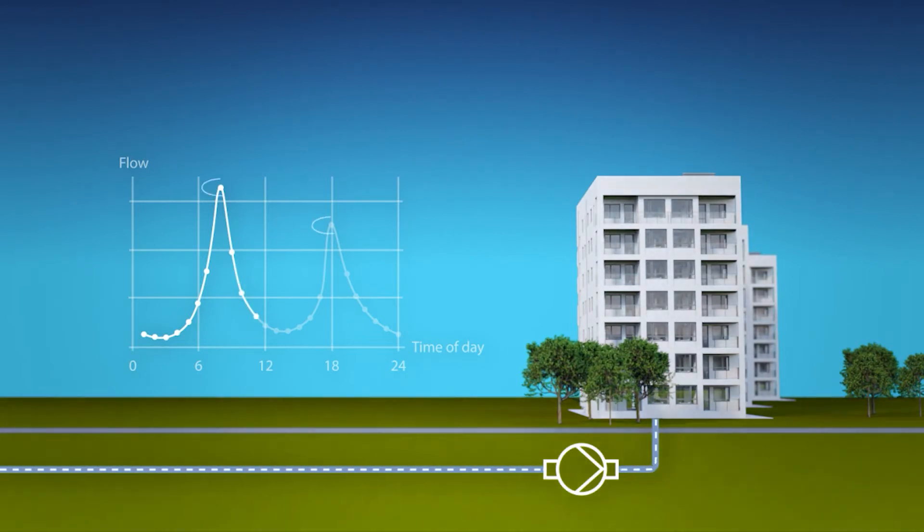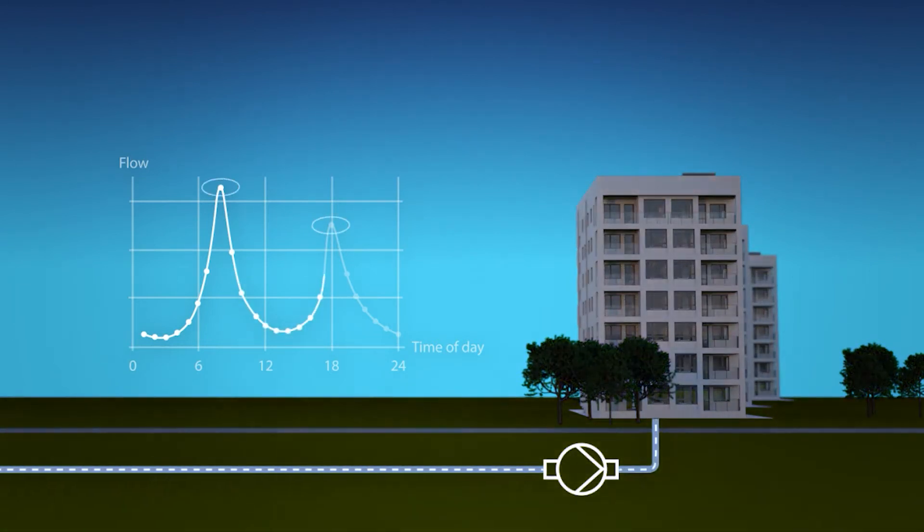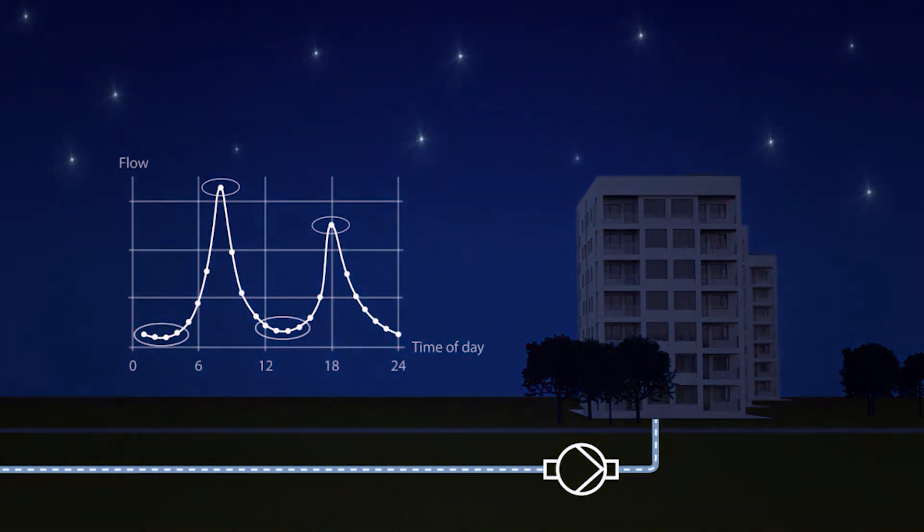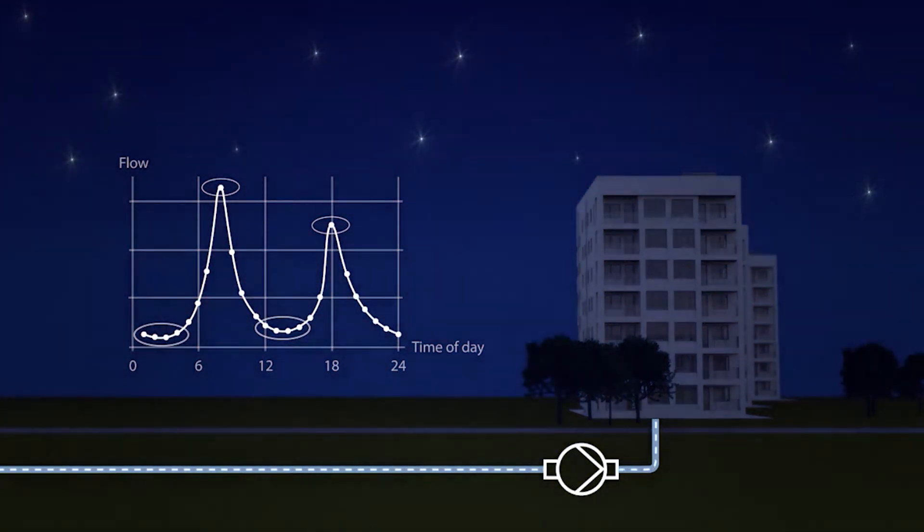At high flow, the pressure is kept constant. However, in periods of low flow, the stop function sets in, shutting down the last pump in operation to save energy.